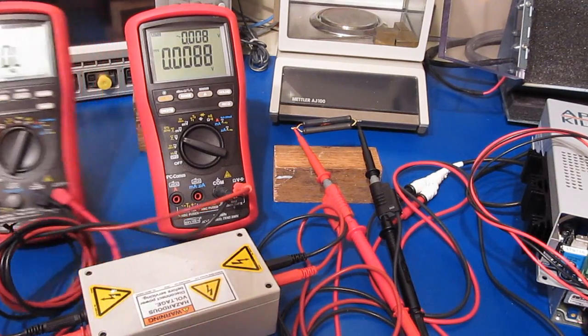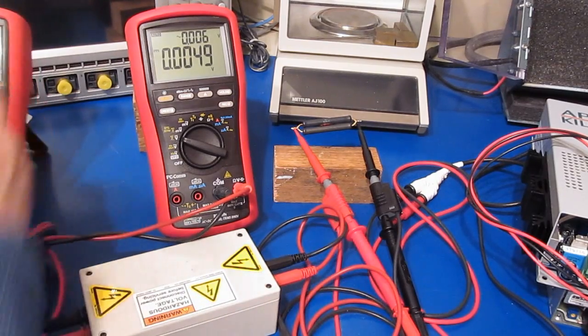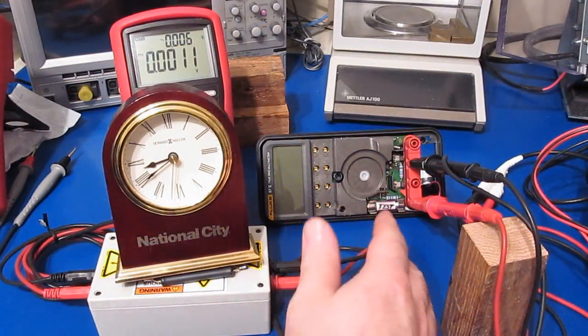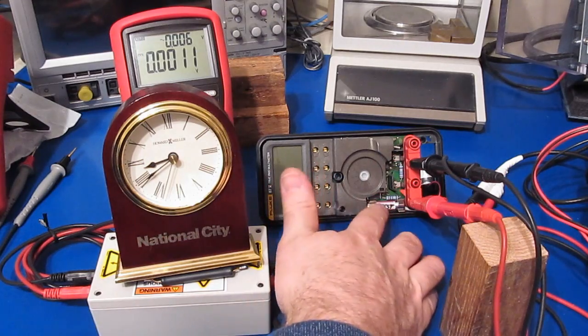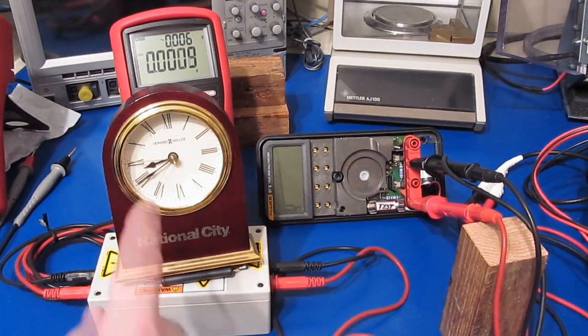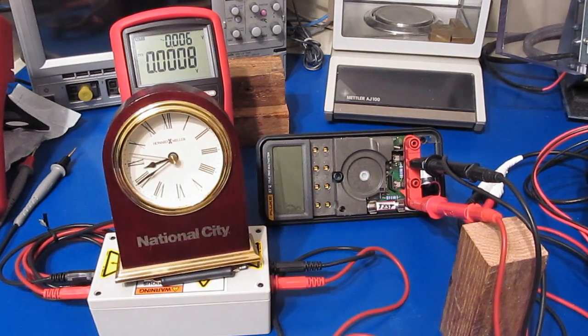Let's get our meter set up and try to repeat this test one more time. Again, we'll be starting with our 10 amp input. You can see I have my test fuse installed. We'll be applying 2 kV for 1 minute as per the IEC standard. So here we go.